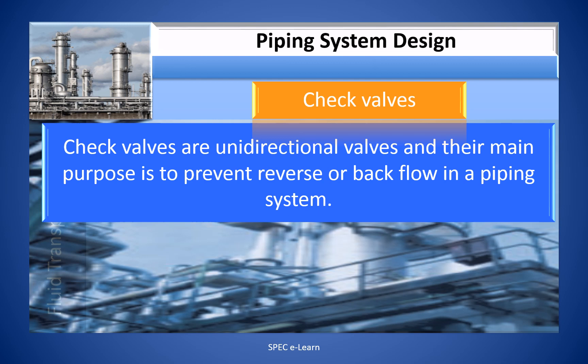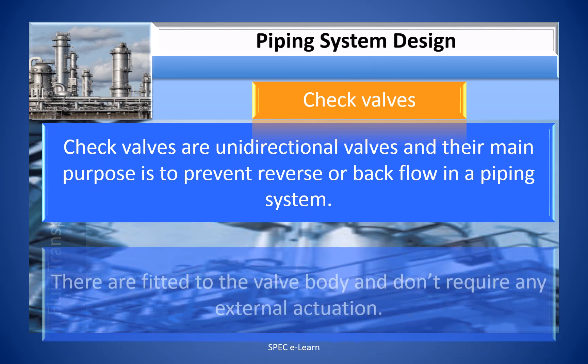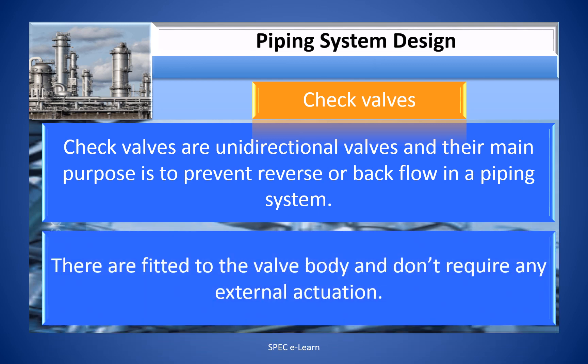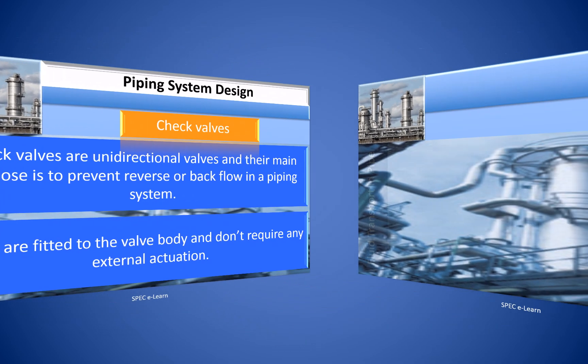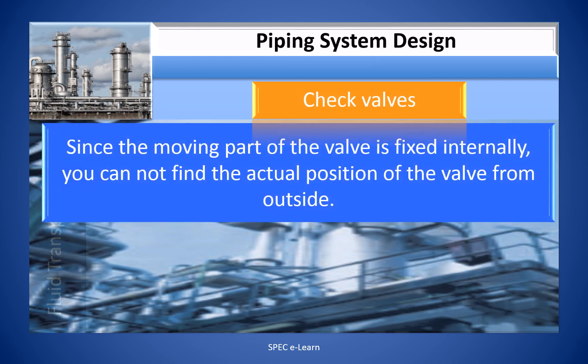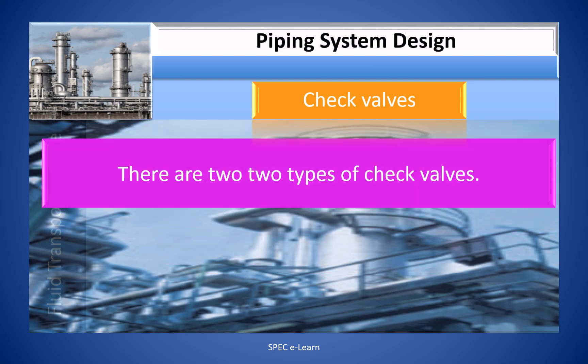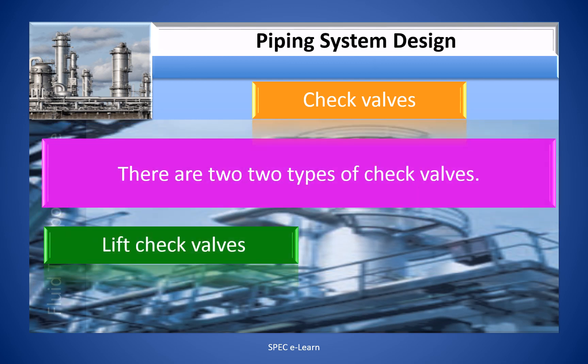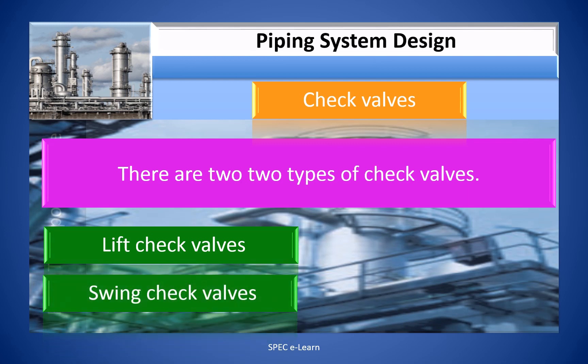Check valves are unidirectional valves and their main purpose is to prevent reverse or backflow in a piping system. They are fitted to the valve body and do not require any external actuation. Since the moving part of the valve is fixed internally, you cannot determine the actual position of the valve from the outside. There are two types of check valves: lift check valves and swing check valves.